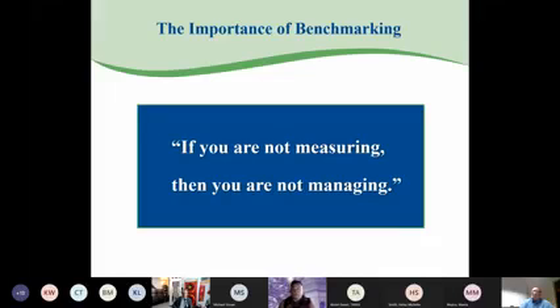So how important is benchmarking? Benchmarking measures key operating factors. You must assess the current situation by using monitoring and verify that processes are operating at acceptable limits. Benchmarking provides us with useful information for trend analysis and helps us to understand cause and effect and the relationship between processes. How can you improve the process if you don't know what the process is doing? I've often heard said it feels hot. What does that really mean? We must have some method to measure the performance of our system, using benchmarking in areas where savings opportunities have been found. I like the statement, if you're not measuring, then you're not managing.